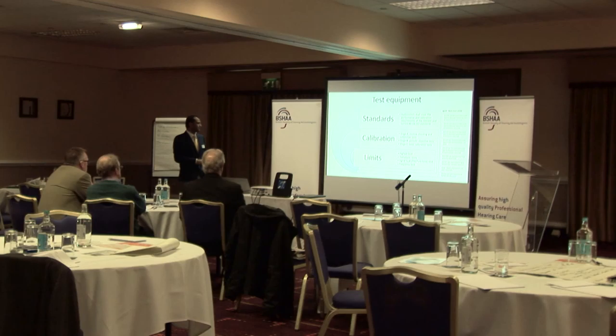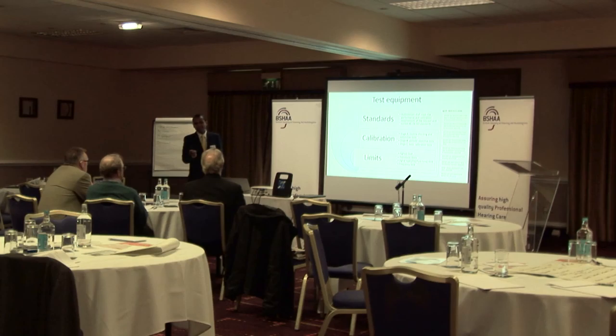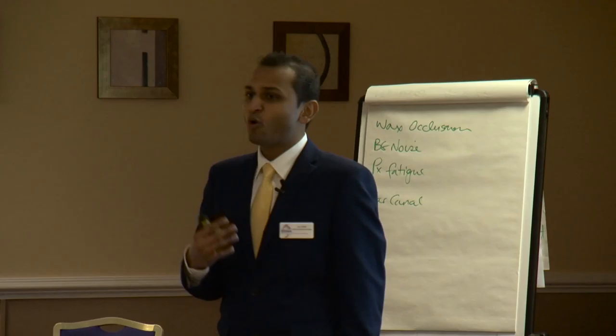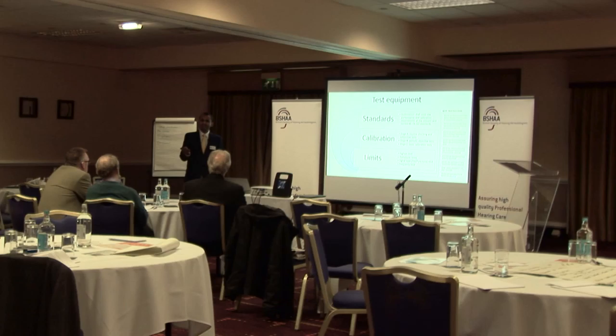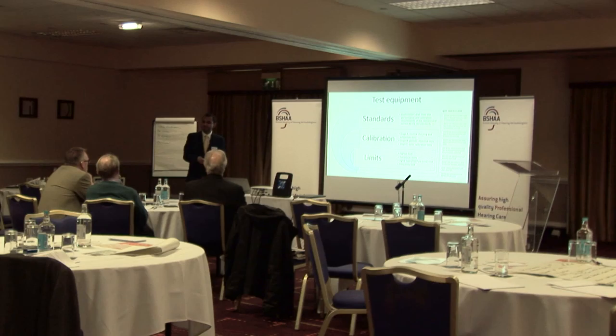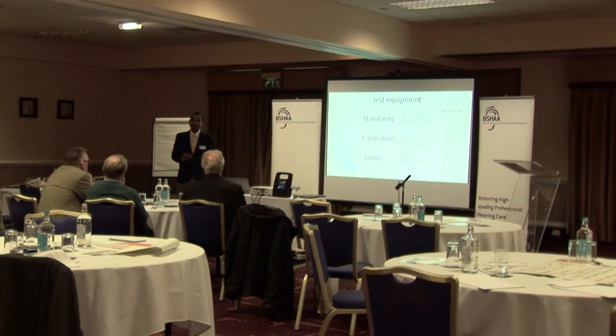Equipment factors include the highest output limit. Levels above 100 dB HL can only be accessed through a special button — if you go to the Health and Safety Executive Control of Noise Regulations, going above 100 dB requires care. If you're audited and somebody says you haven't been careful, how do you prove it? You need an extended range button on your audiometer, and you must record that you asked the patient and they were comfortable with you proceeding in 5 dB steps above that level. All of this has to be in your local protocols.